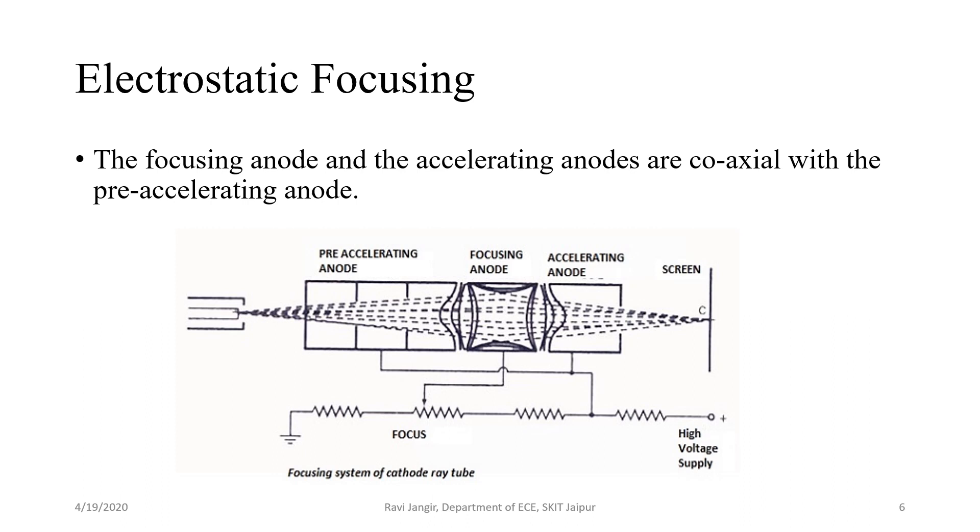The equipotential surfaces thus form a double concave lens. The electron beam entering the field at angles other than the normal to the equipotential surfaces will be deflected towards the normal and the beam is thus focused towards the center of the tube axis. By changing the voltage of the focusing anode, the refractive index of the electron lens can be changed. And therefore focal point of the beam can also be changed. The change in voltage is brought about by changing the setting of a potentiometer. This control is brought to the front panel of the CRO and is marked focus.